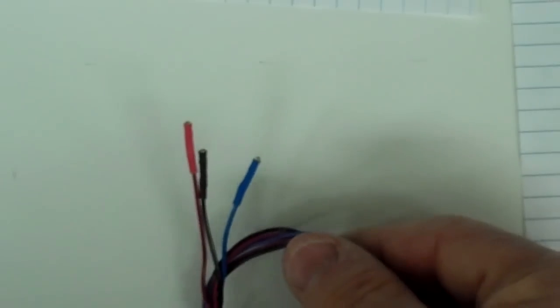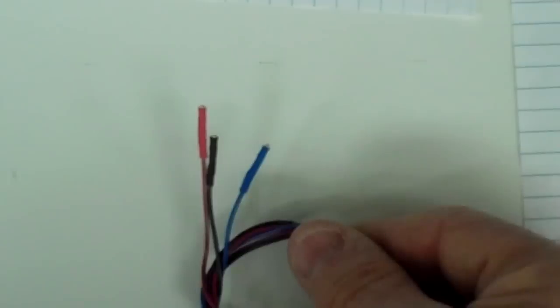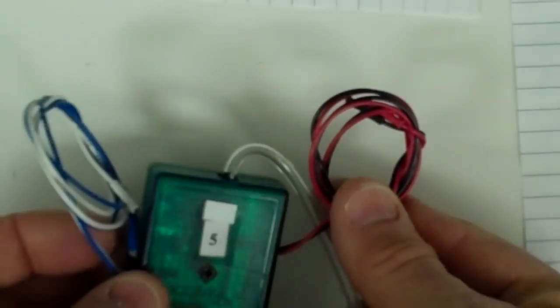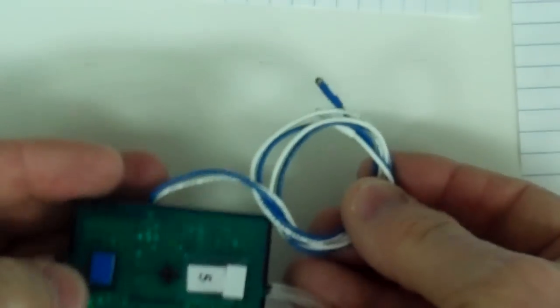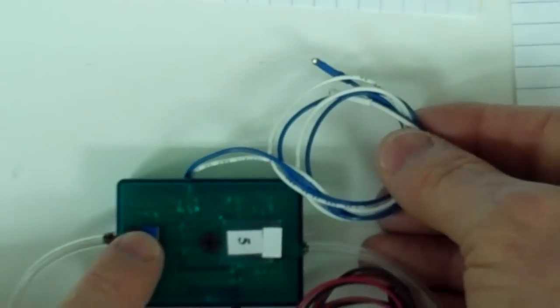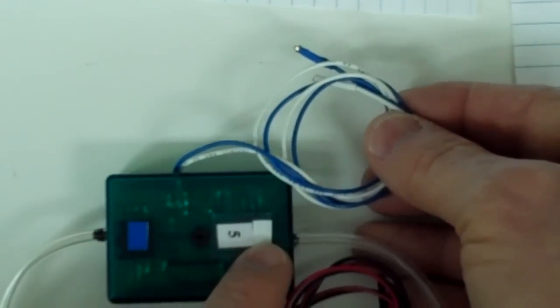All of the other sensors basically are configured to have a black, red, and blue, since they're single sensor output, except once more for the 2 pressure transducers. And you can see here with the pressure transducers, we have the ground and power supply, but we have 2 outputs: a blue output for this transducer and a white output for that transducer.